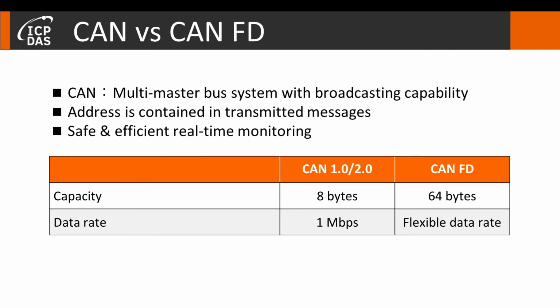CAN is a multi-master bus system with broadcasting capability. In the CAN protocol, the bus nodes do not have a specific address. Instead, the address information is contained in the identifiers of the transmitted messages, indicating the message content and the priority of the message for arbitration. It provides safe and efficient real-time monitoring.